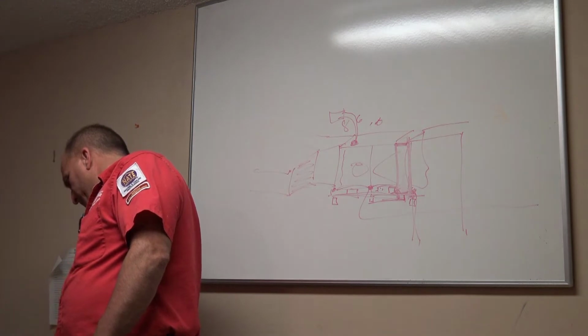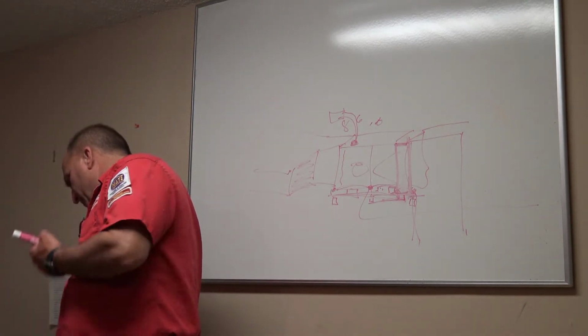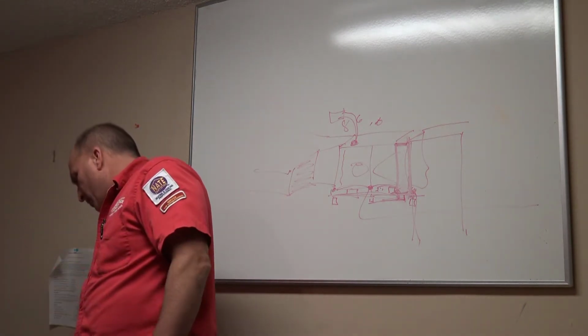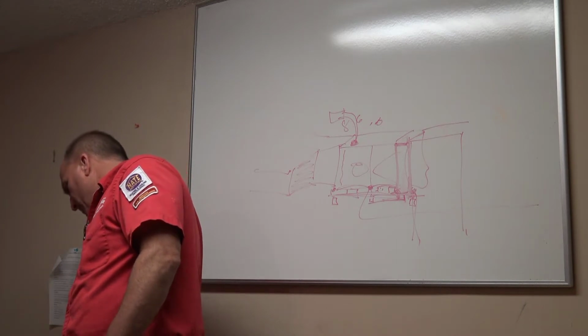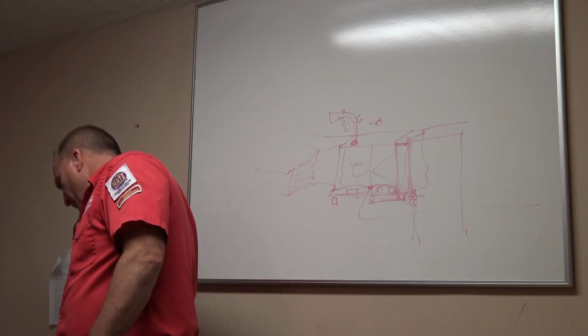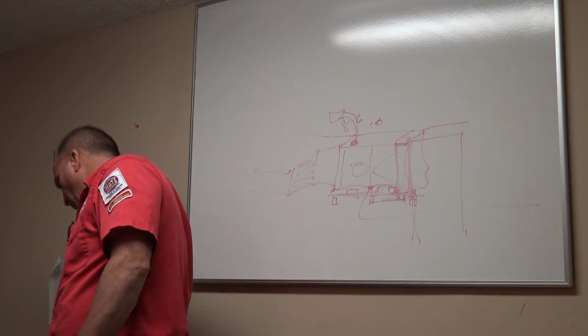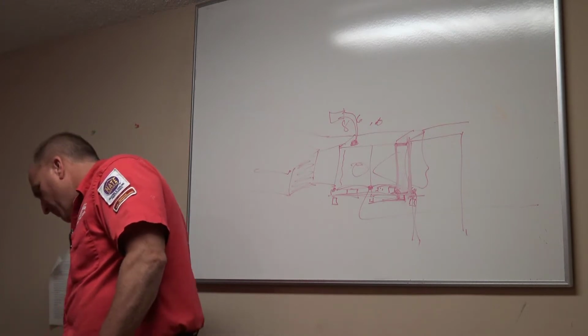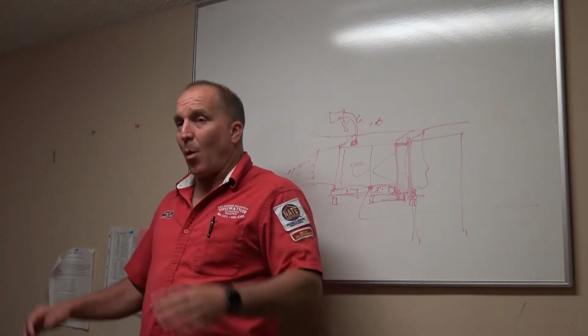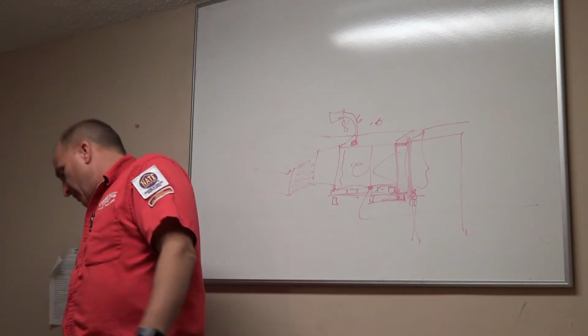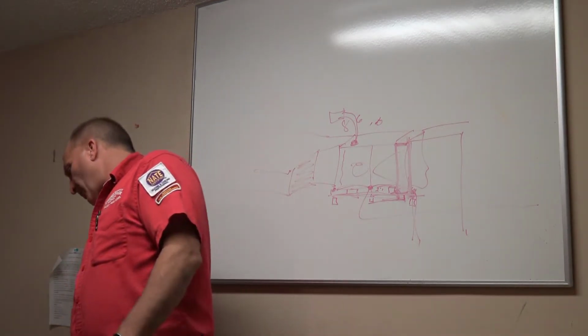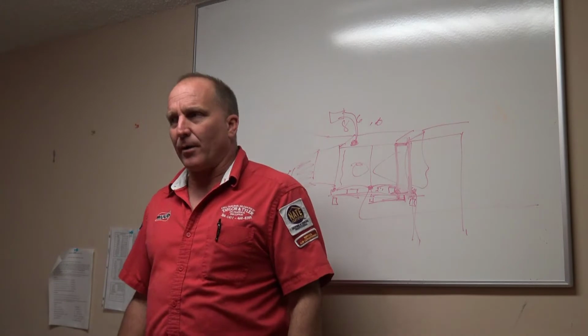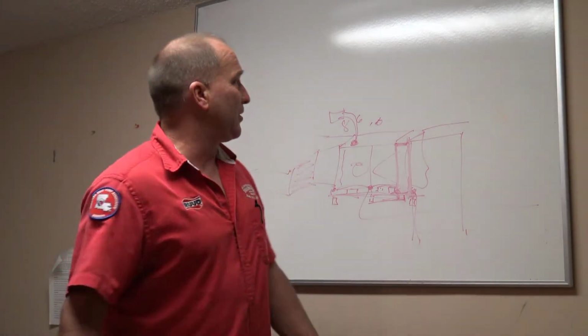Wiring. Check wiring for proper size, condition, tighten wires on all breakers, air handlers, and disconnect boxes. Look for discolored fuses, burnt or charred wires. So number 2 is wires. You're checking wires, and I'm asking you, are they okay? Are they burned? Are they miswired? Well, what are you doing? What am I actually checking for on the wires?